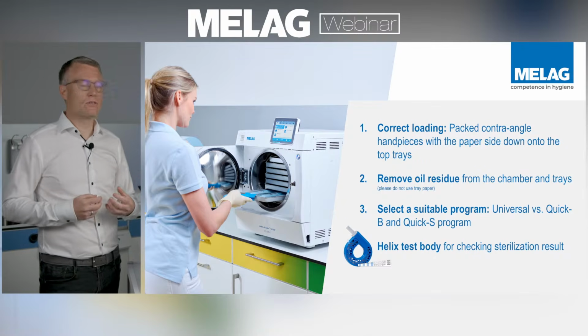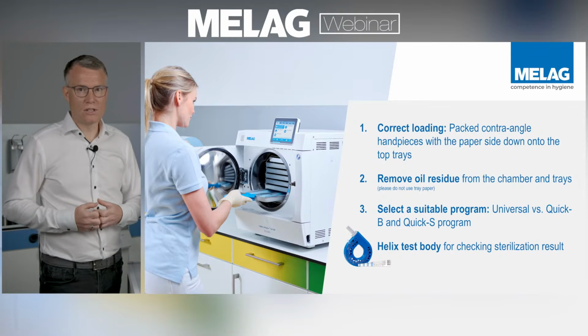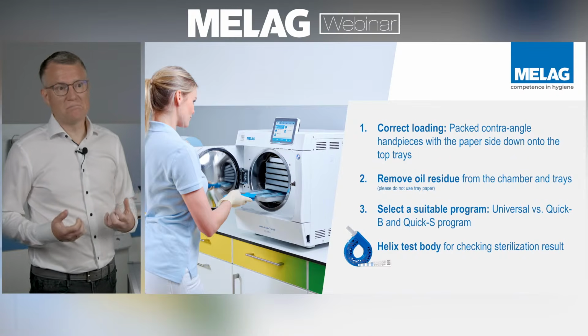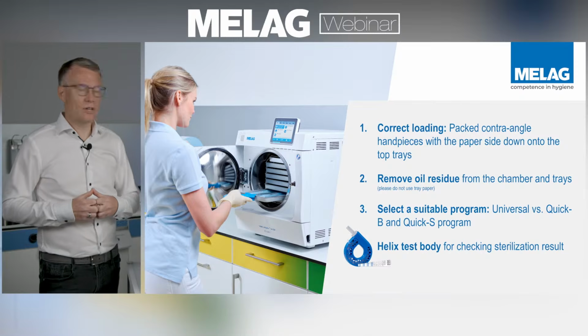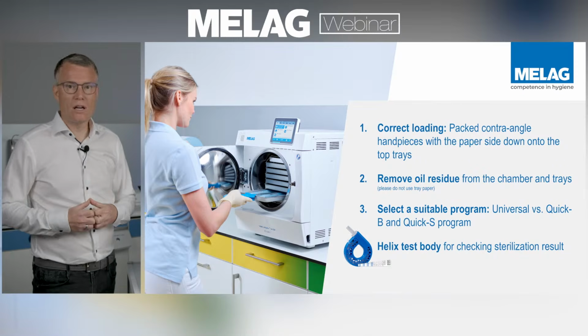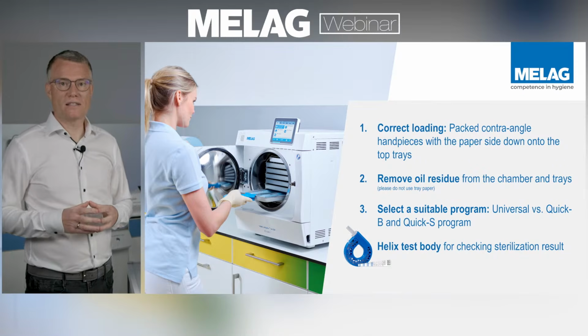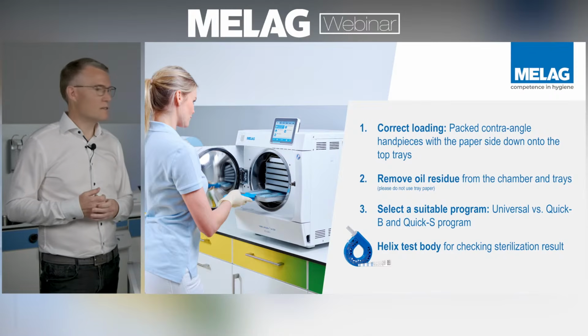Then of course, depending on the load, wrapped, unwrapped instruments, hollow body instruments, non-hollow body instruments, we need to choose the correct program according to the load. Most common, probably inside dental clinics and practices, is the so-called universal program. However, there are quick cycles available, quick S and quick B cycles.